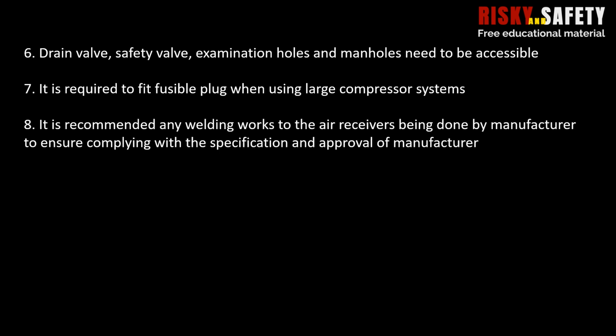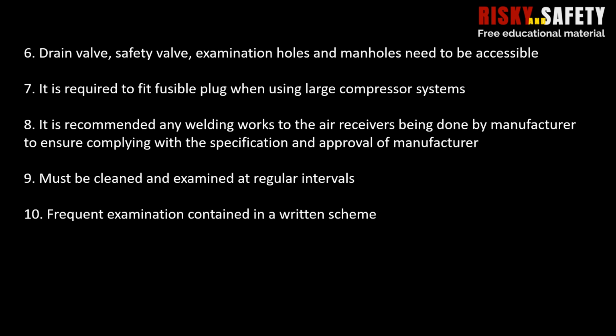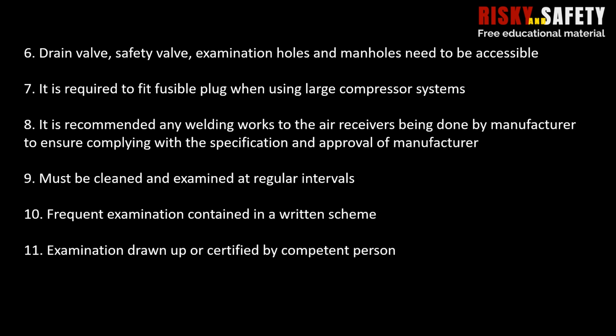It is recommended that any welding work on air receivers be done by the manufacturer to ensure compliance with the specification and approval of the manufacturer. They must be cleaned and examined at regular intervals. Frequent examination is contained in a written scheme of examination drawn up or certified by a competent person.